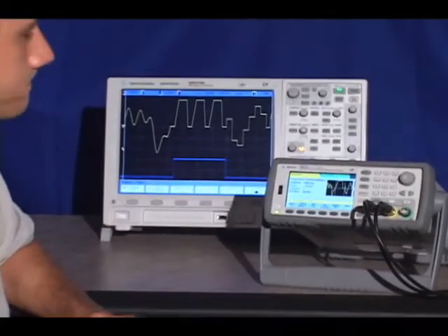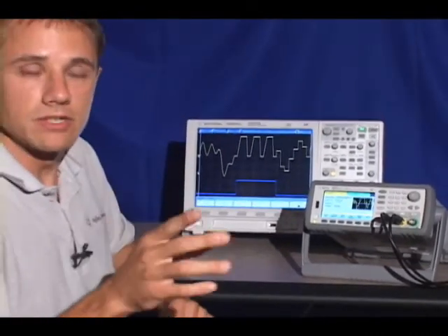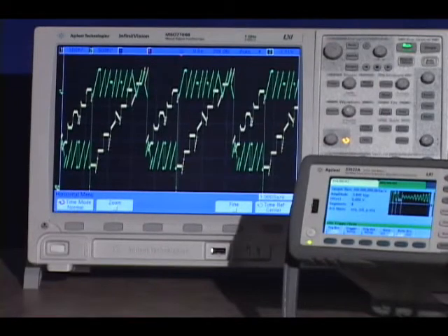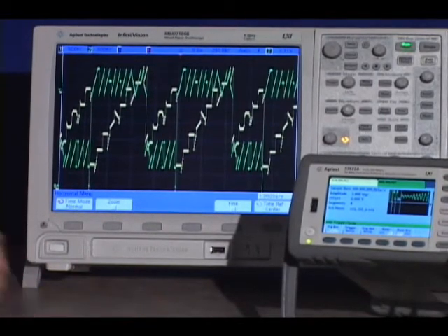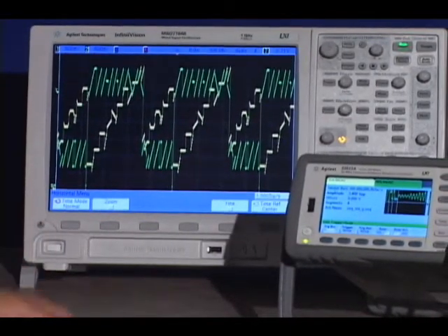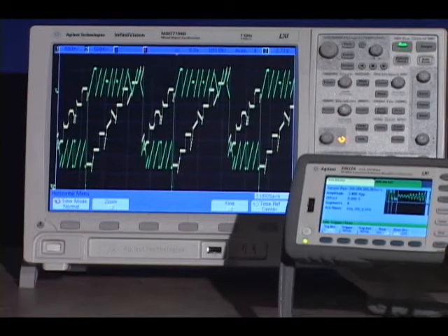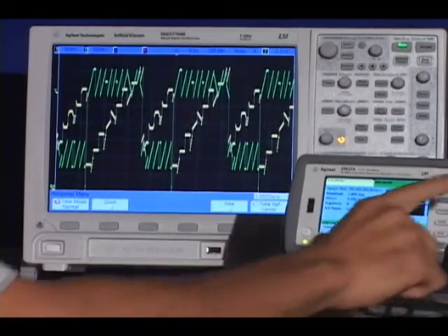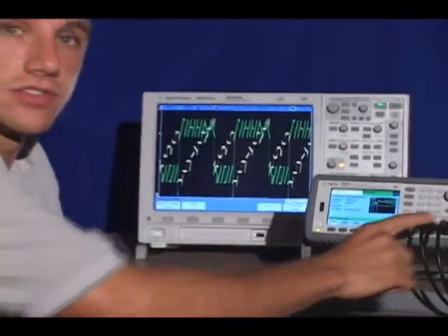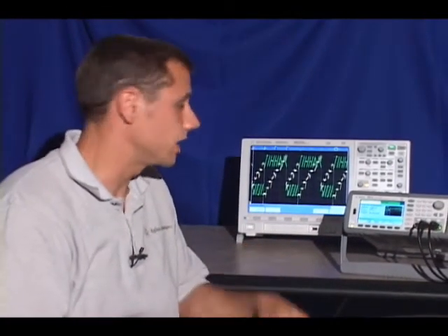Or I could use triggering. Let me show you an example where I use triggering. This time I have a sequence set up with three waveforms to transition from one waveform to the next using triggers. Actually I have two sequences. One on channel one and one on channel two. Channel one is in yellow and channel two is in green.